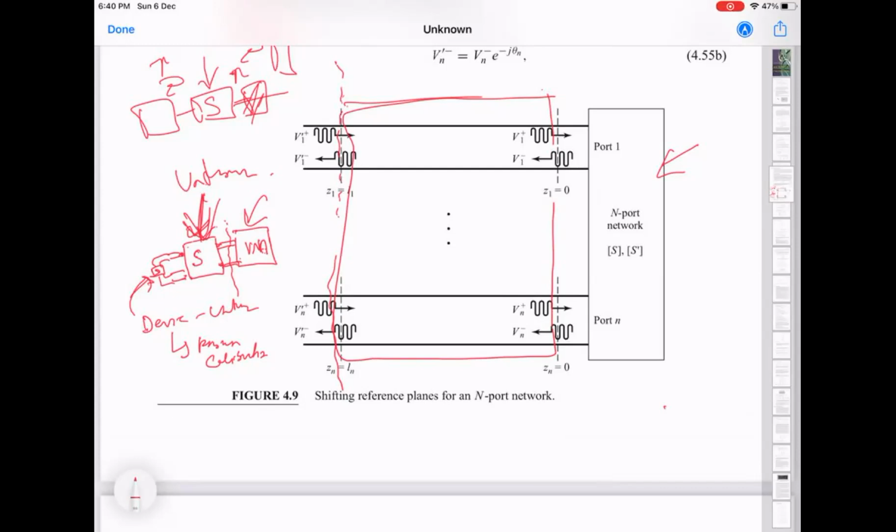So that's why I said that for the simplest case where it's just a long length of cable, you can just dial the electrical delay and then it's fine. But what it will not give you correctly is the reflection coefficient. And in fact, I'm going to move to Microwave Office now. I'll explain why that is the case. It's actually fairly straightforward, but it's good to see under what conditions which quantities are going to give you the information you're looking for, and which are not going to give you the information when you don't know the unknown object. Okay. Anything else?